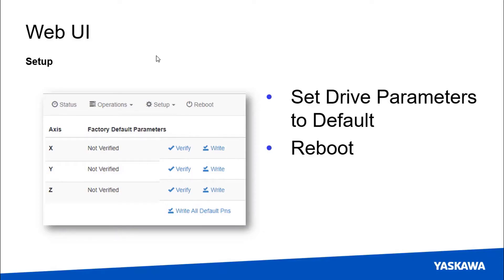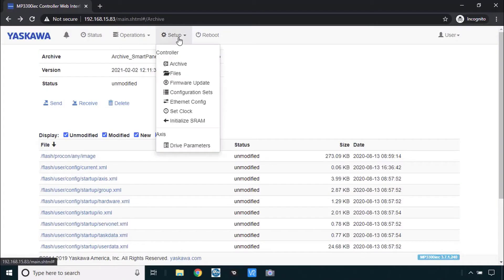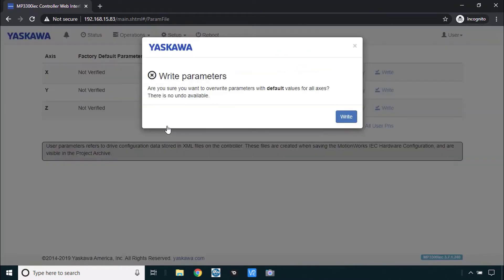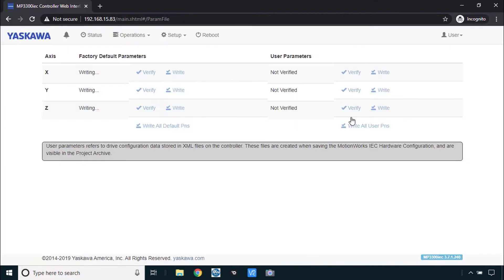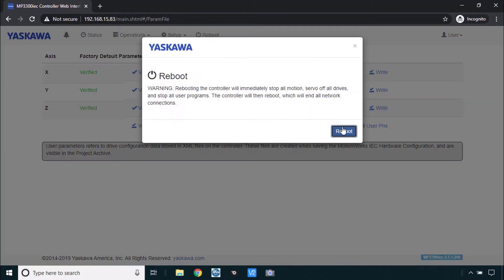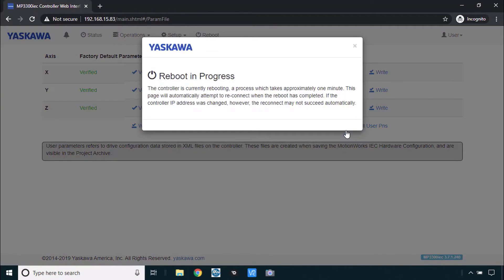One more step here. Now that we've got the right configuration we want to send default parameter set down to each of the axes. You just go to setup drive parameters. And then here on the left side factory default write all default PNs and confirm with write. That just takes a few seconds. It will have this green text verified. And one more reboot we will be ready with the controller.